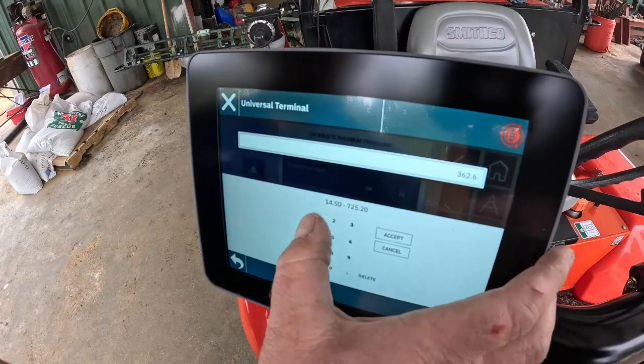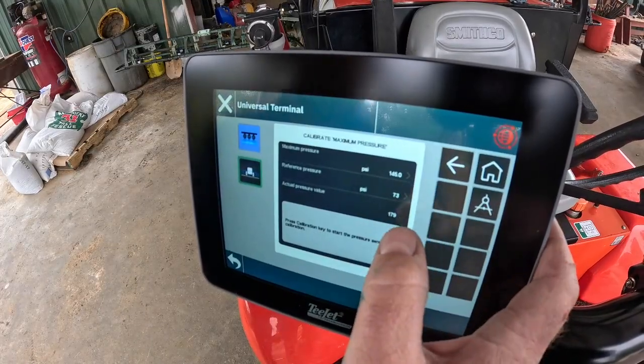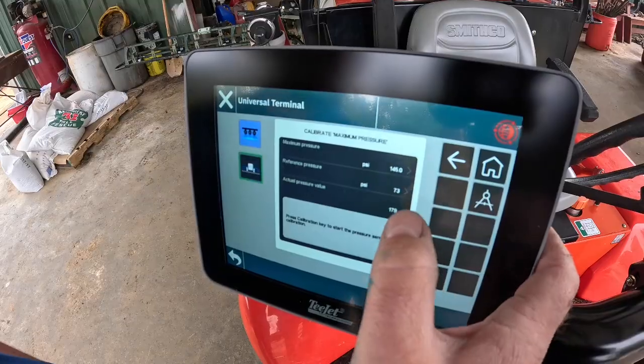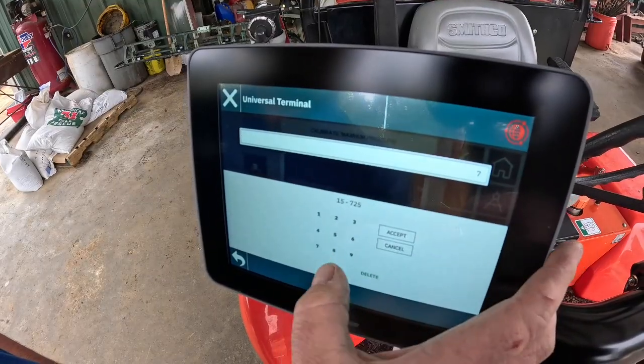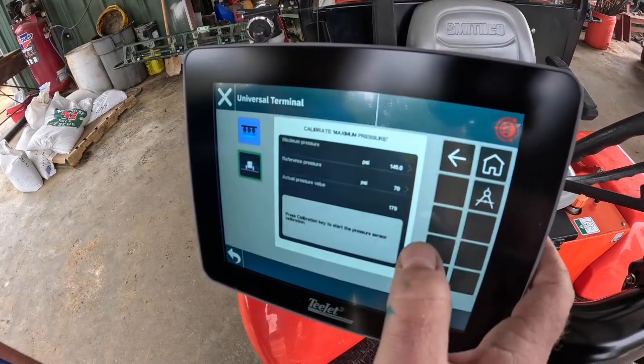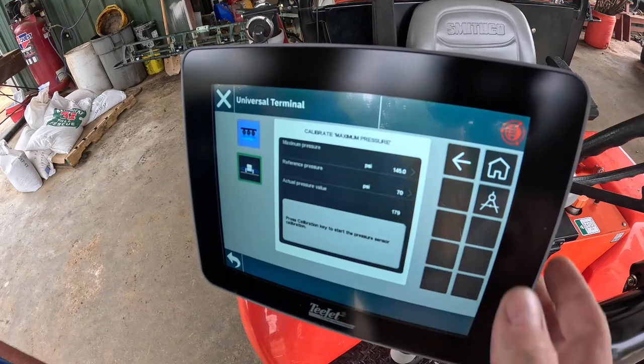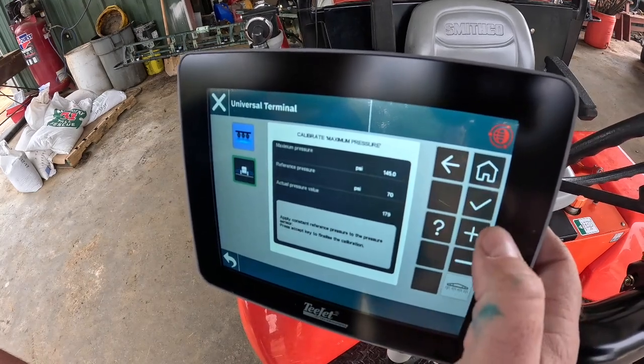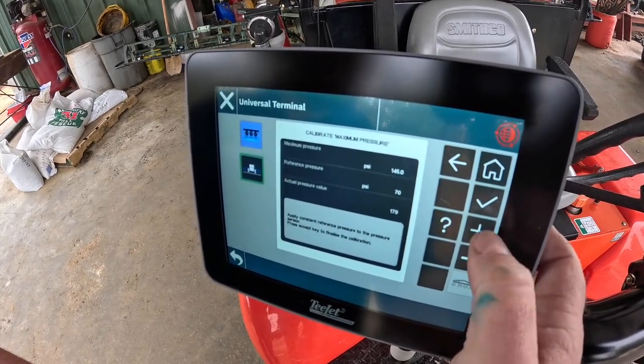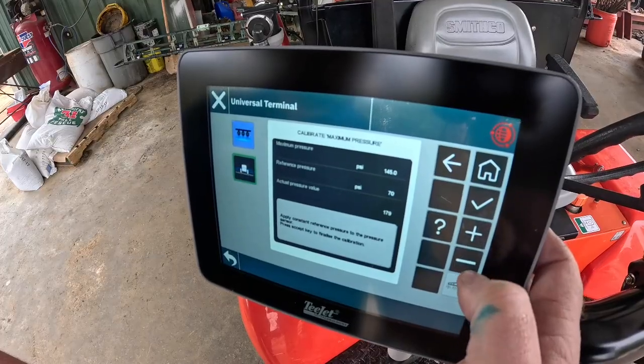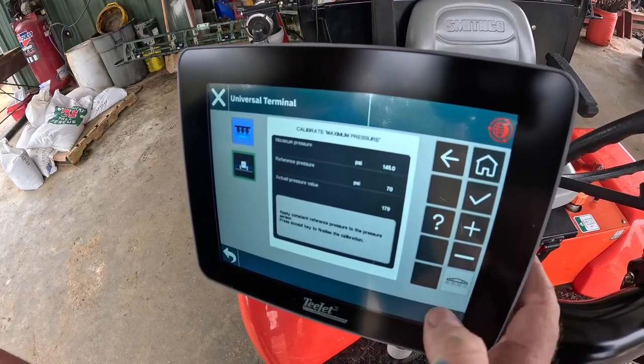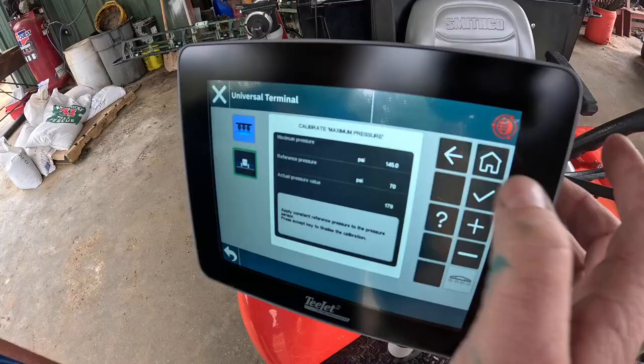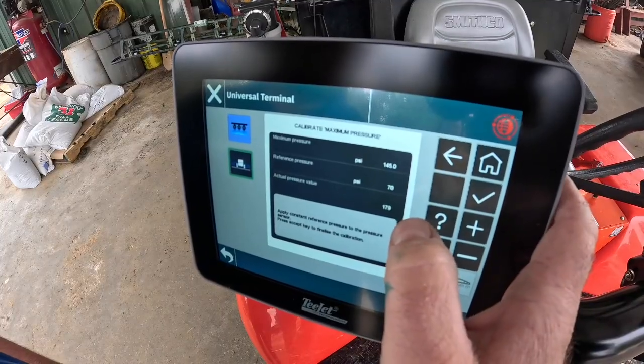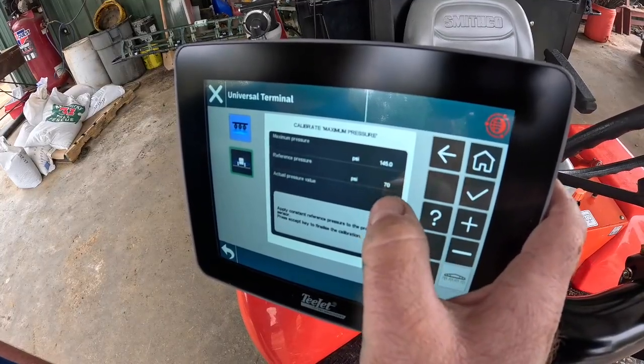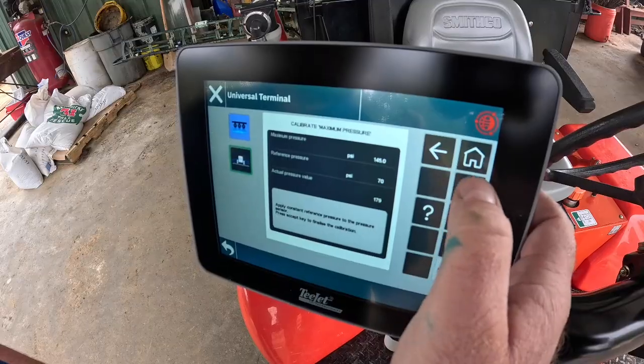So with maximum pressure, you're going to do the same thing. So we have a 145 PSI pressure sensor on here, and it's got a reference pressure of 73, which is kind of hard to read on a gauge, so let's just put it at 70. And here what you would do is you would hit the calibrate button, turn your sprayer on, and use the plus button to increase pressure, the minus button to decrease pressure, and run your manual gauge. You'll look at your manual gauge and get it to 70 PSI, which is your reference pressure, and then you would hit the check mark.